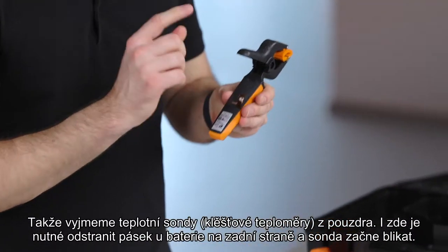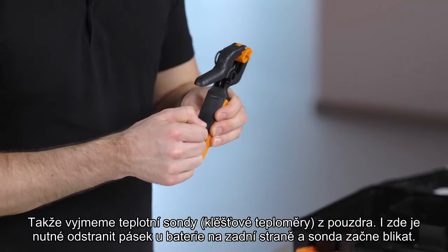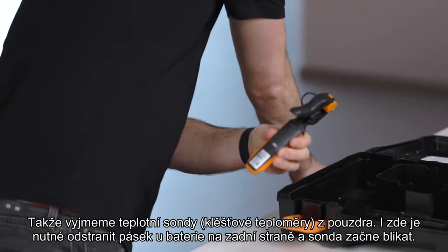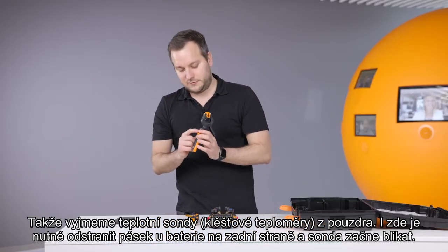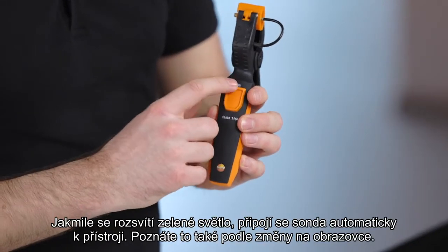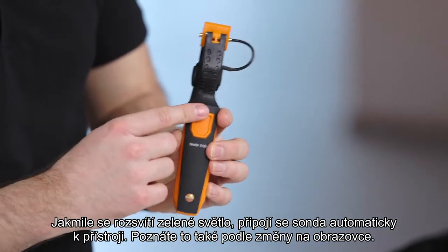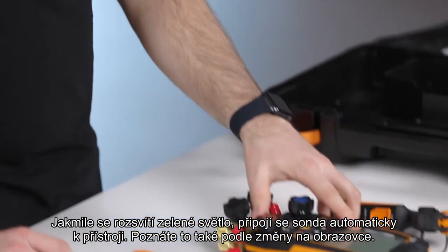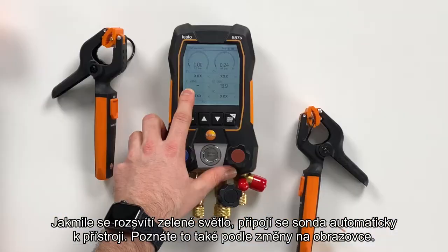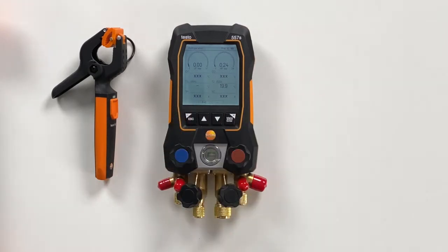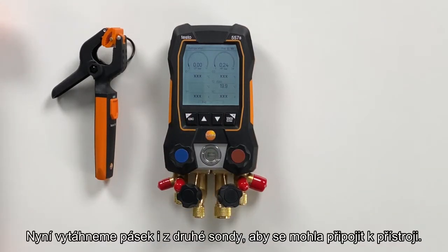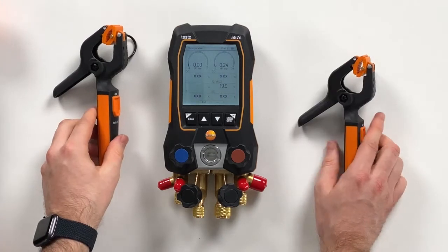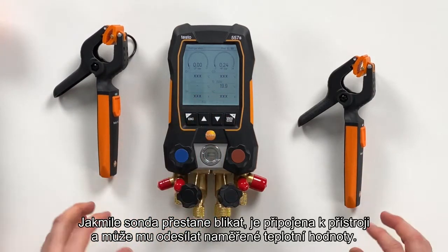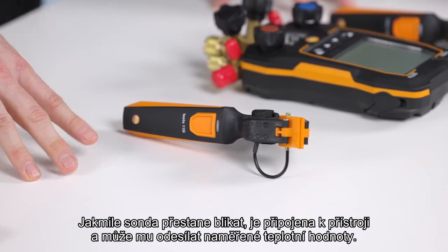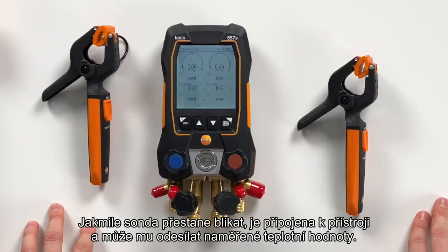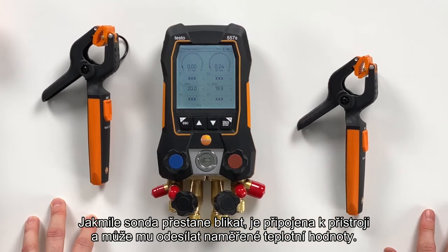Also on these probes we remove just the strap on the back of the housing, and we can see directly that the probe switches on. It looks for connection. Green light shows the probe is connected. We can also see it in the display that the probe is connected now. And we will also connect the second probe. And you can see how the display switched. So it's scaling based, is there a probe connected or not. Now we have both probes connected and are ready to measure.